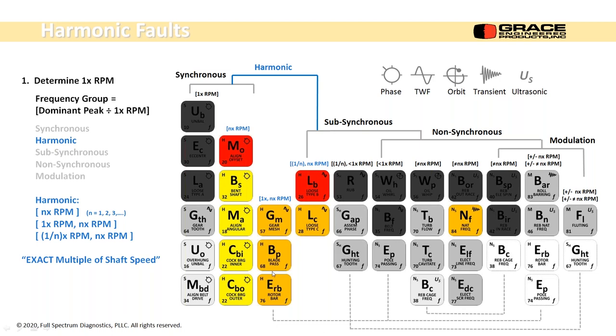If I have a pump with 5 blades, I'm going to get exactly 5 times running speed. And it's a pulsation in pumps and fans and compressors when a fluid is compressed past an obstruction. So in a pump, it's a cut water. You'll squeeze that fluid, whatever it is, and it'll pulse as each blade goes by that cut water.